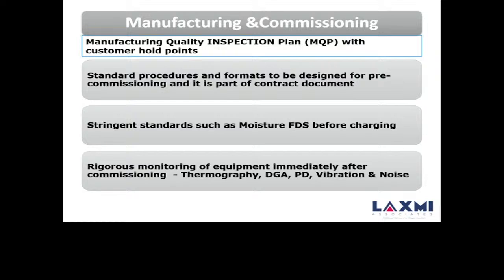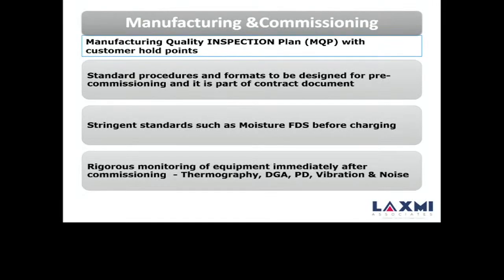Then moisture measurement, FDS at the factory, if you do it, is very good, because the life of the transformer is decided once you dispatch it from the factory. As we are talking a lot about moisture here, when there is moisture we try to find some solution. But once you have benchmarking at the factory itself, this is my moisture content, and this is how dry or wet a transformer we are taking from the factory, it gives you a thumb impression that we should not bother about the moisture most of the time. We should bother about the other problems. So one problem can be solved here.